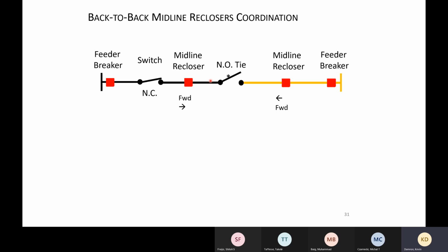So both those reclosers, if I put a fault past them, if I put a fault right there, if I put a fault here, and this breaker is going to open, right? Nothing's going to happen on the other feeder. But again, if I had this feeder breaker out, I can close this switch, and now the two feeders are tied together. And the big change is we started using directional elements, where in traditional feeders we had no use for directionality. Now directionality becomes important, and we use it to coordinate the number of recloses.